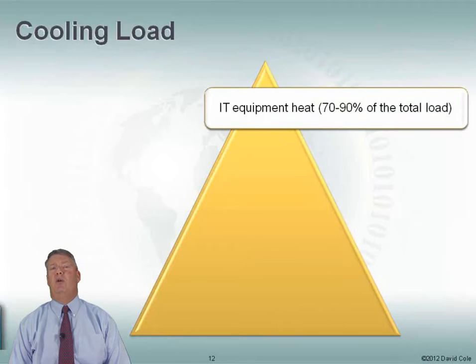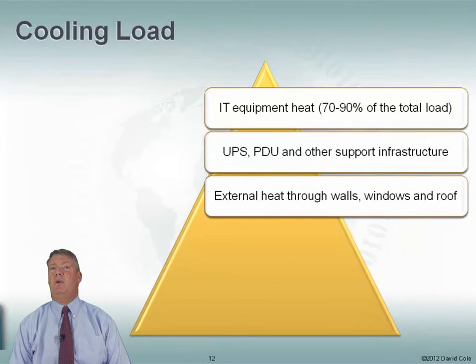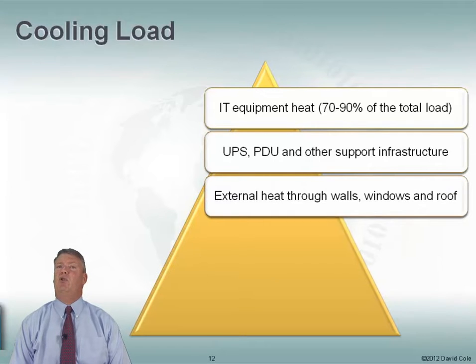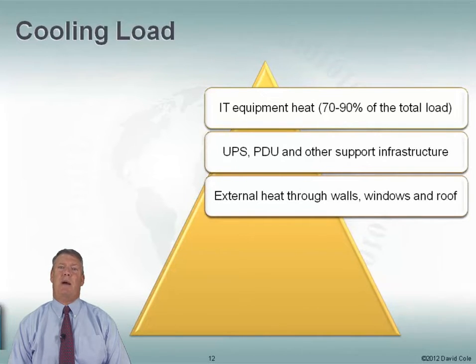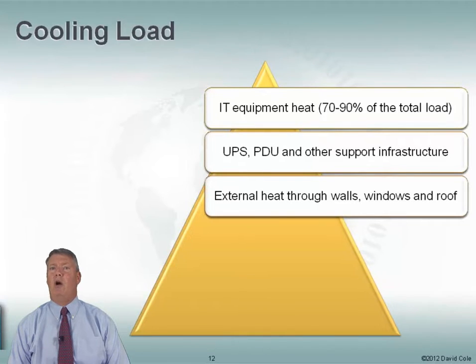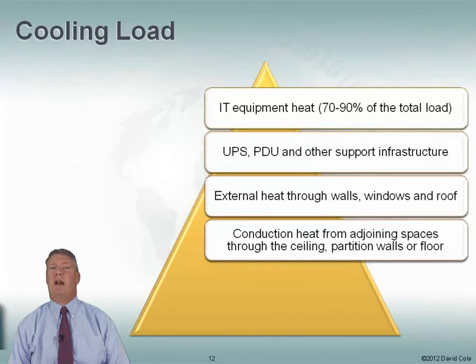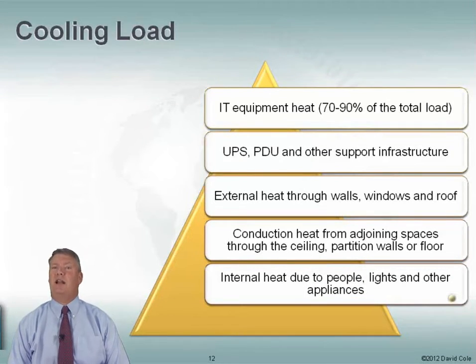We have to know what it is we're cooling. IT equipment makes up a big portion of the load, along with UPSs and PDUs. We might also get external heat through walls, windows, and roofs — it's why we typically don't put a data center on the top floor because of the heat through the roof, and why we typically don't put windows in a data center. We put a data center inside of a building, not against an external wall, so we don't get that heat generation through external walls. And whenever we open up a door to the data center, if it's hotter outside, that heat is going to come in.